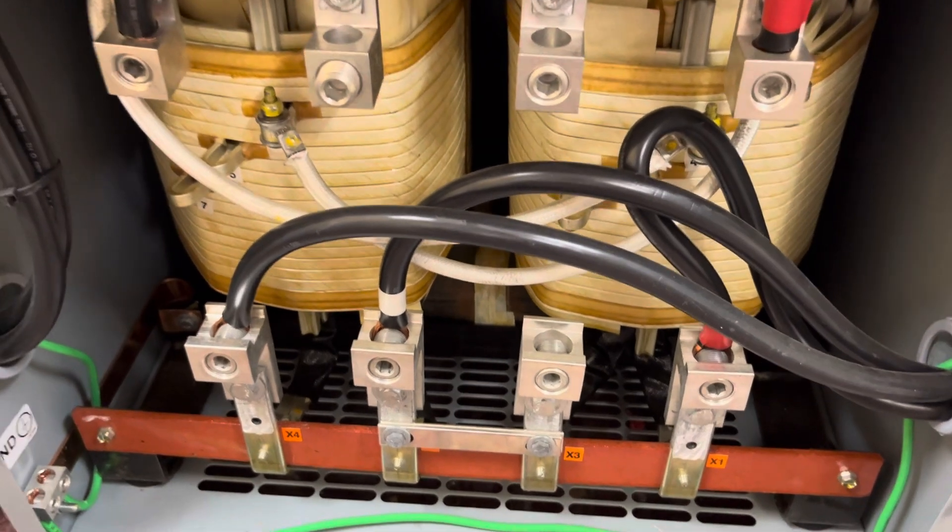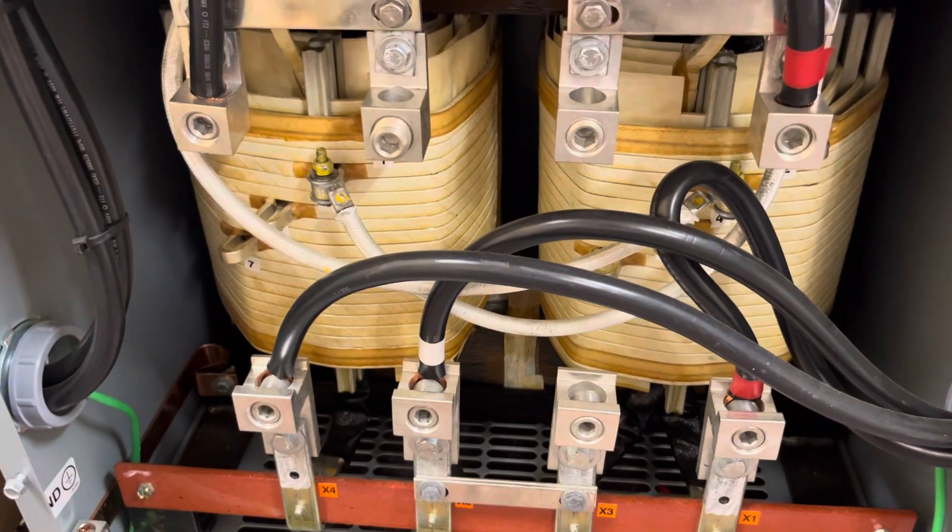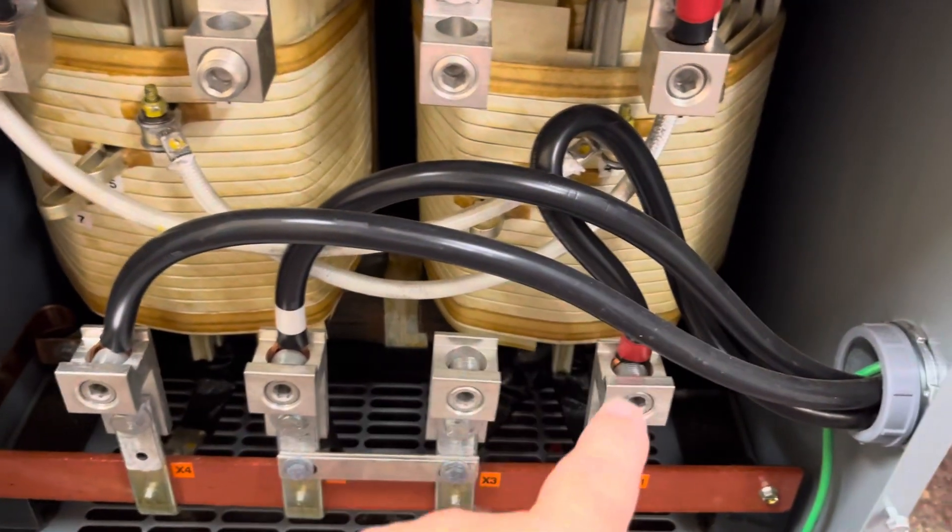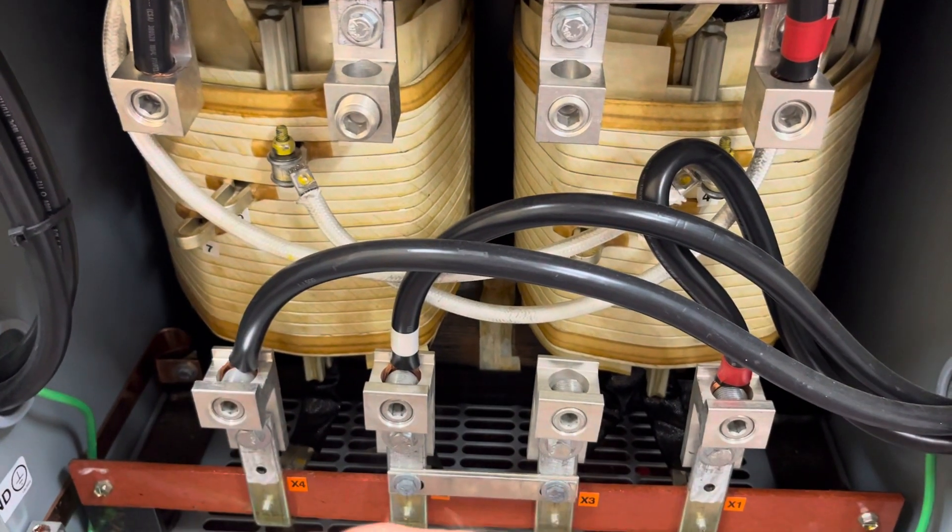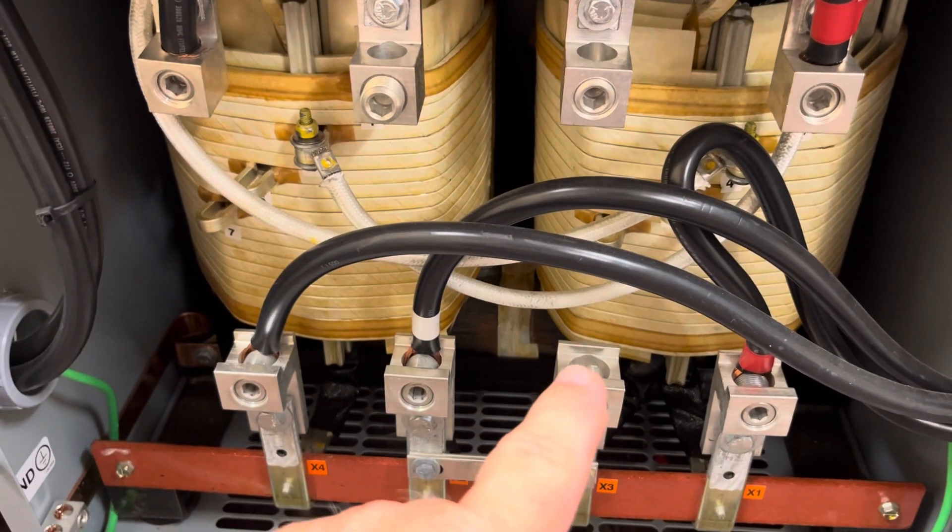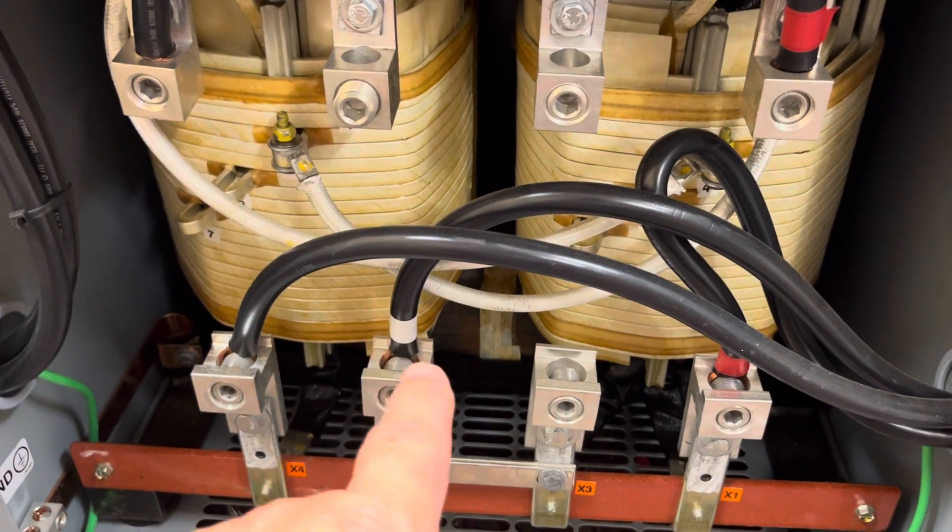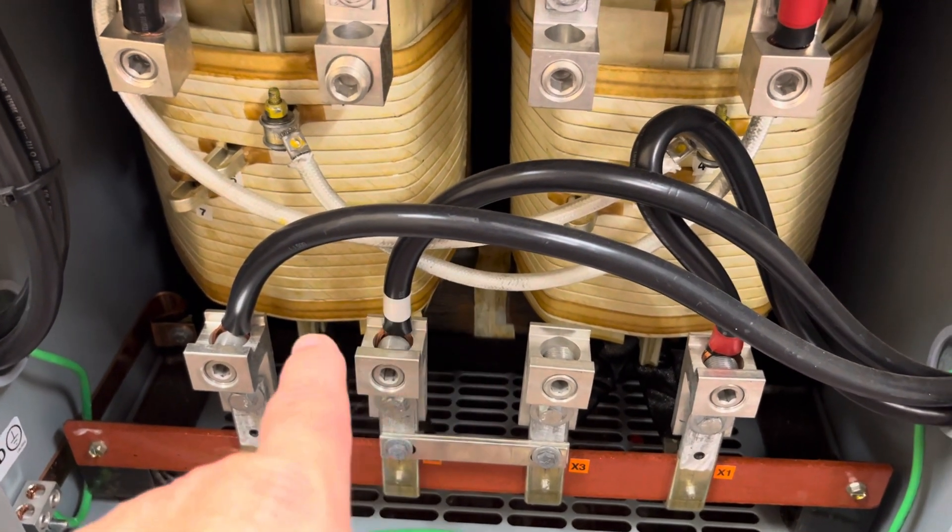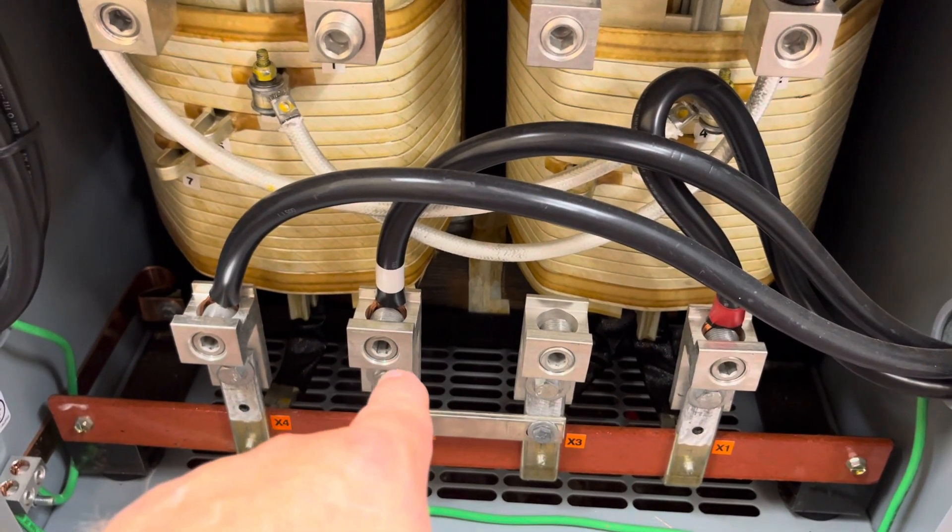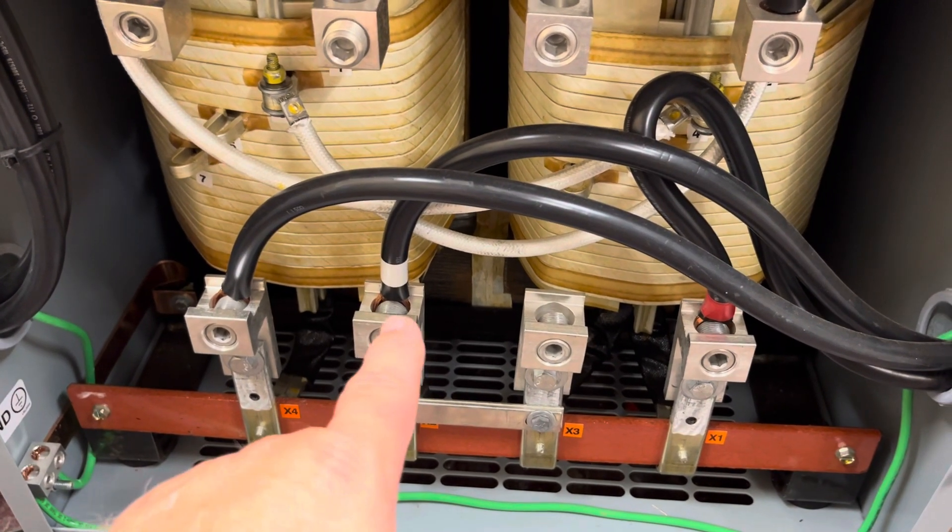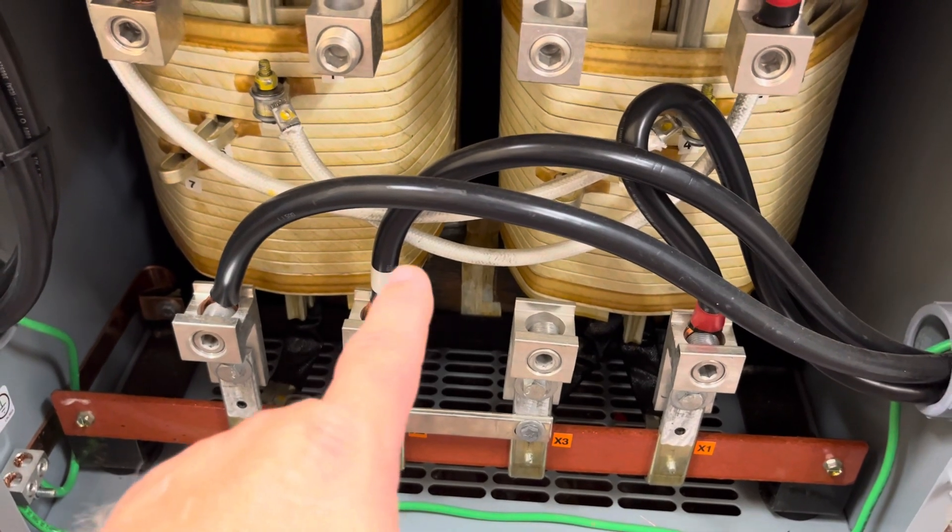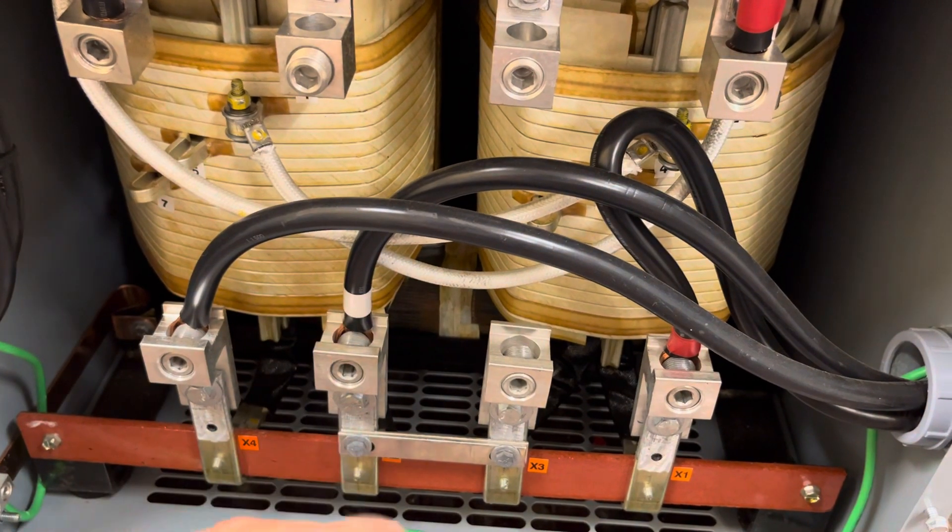But that creates a problem when you're in bypass mode. Because when you're in bypass mode, L1 and L2 from the grid pass straight through. And it already has a reference to neutral. It already has a neutral from the grid. And that neutral is bonded at your first panel. So what you end up doing when you're powering from the grid is you're creating a second neutral. That's going to be in parallel with the grid neutral. It's also going to be bonded to the ground. So you end up with a ground loop.